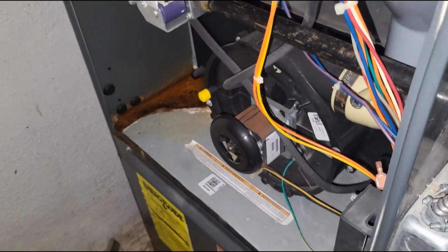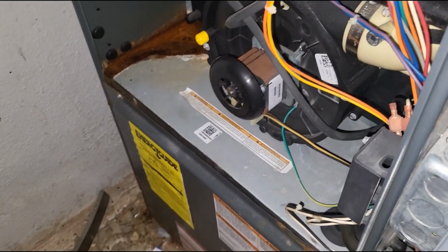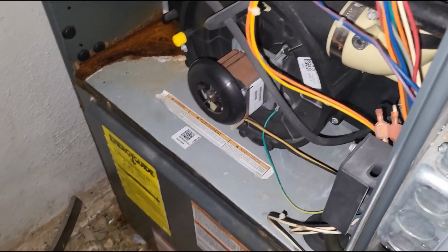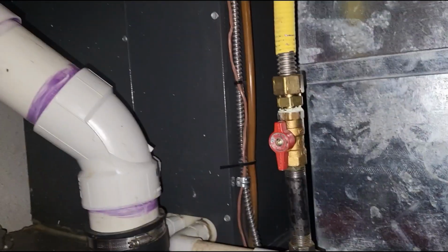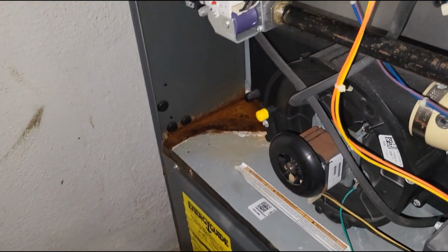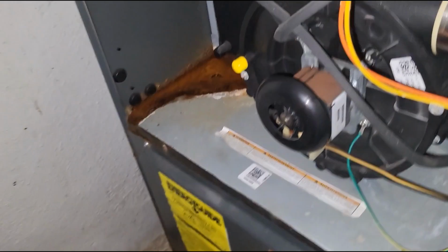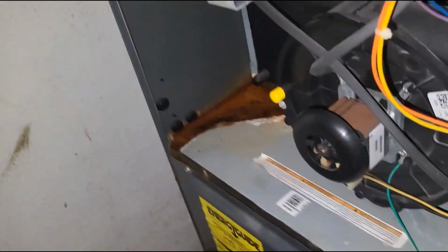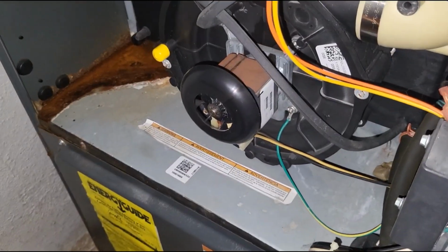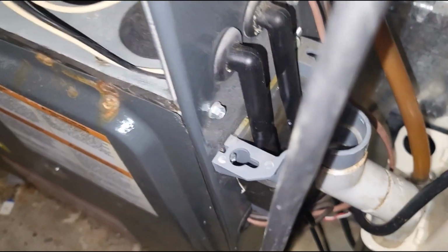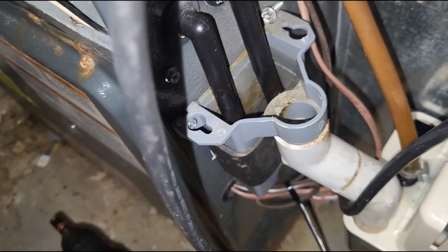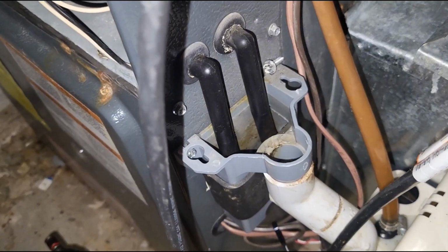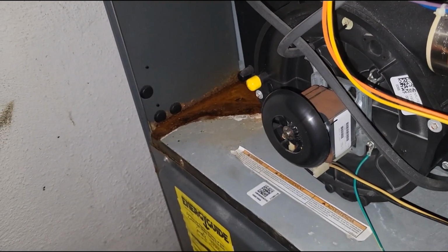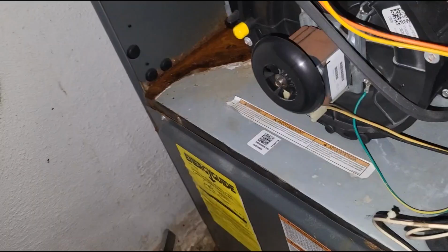I know this unit was here when this customer moved in, but they didn't have any service history prior to us coming out, I believe 2 years ago. So 2 years ago, when we did the capacitor replacement outside, that's when we signed this customer up for maintenance. But anytime, especially with 90% units, anytime we see rust or any previous water damage, we always step back and make sure that this furnace is draining, meaning the condensate trap.